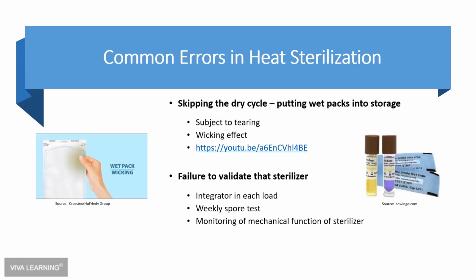In some, not all, but some sterilizers, there are two different heating elements: one that creates the heat for the sterilization cycle, and one that creates the heat for the dry cycle. So that heating element for the dry cycle might not be functioning. Make sure that nobody takes instruments out unless it's absolutely necessary, because you've got to use them right away. And if you can't wait until your instruments go through the dry cycle, you might need a few more instrument setups in your practice.